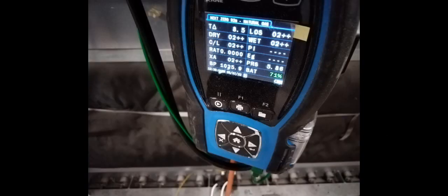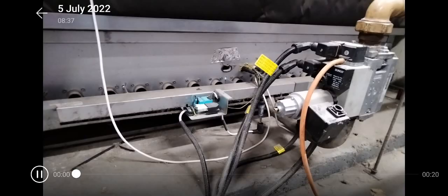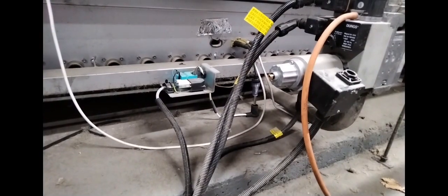Once I was satisfied that the drop test was good, I reopened the gas supply and did a drop test whilst the gas valve was opening on initial lighting of the boiler. Then I ended up with a pressure drop. I could see the gas valve was opening, so I connected my spark plug connector. You can see it's sparking, but despite gas going in and there being a spark, it looked as though it wasn't lighting.